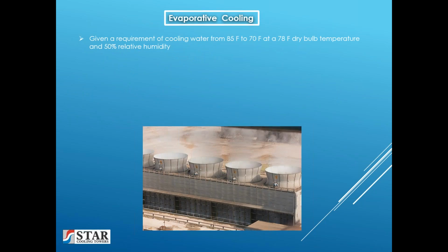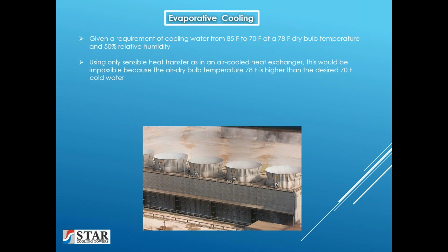If we were given a requirement of cooling water from 85 degrees Fahrenheit to 70 degrees Fahrenheit at a 78-degree dry bulb temperature and a 50% relative humidity, using only sensible heat transfer as in an air-cooled heat exchanger, this would be impossible because the dry bulb temperature of 78 is higher than the desired 70-degree Fahrenheit cold water temperature. The process of evaporation that occurs in a cooling tower makes the solution an easy one.